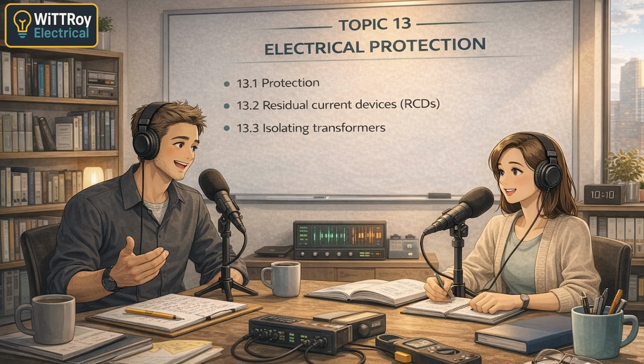Exactly. Now think about electric shock. What normally causes shock? Completing a circuit through the body. Correct. Now if someone touches one conductor on the secondary side of an isolating transformer, what happens? Nothing happens? Close. A circuit is not completed, so current does not flow through the body in the usual way. So the shock risk is reduced. Exactly. Reduced, not eliminated, but much lower.